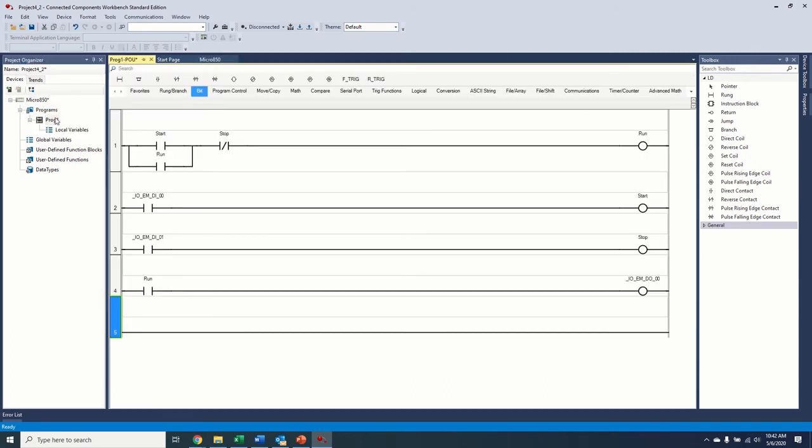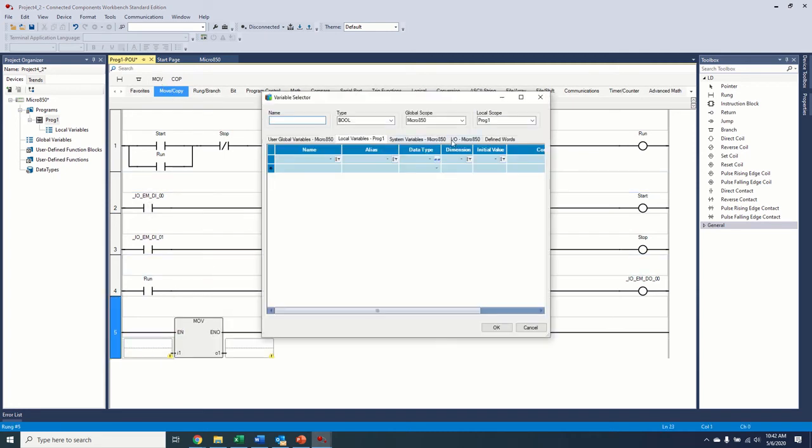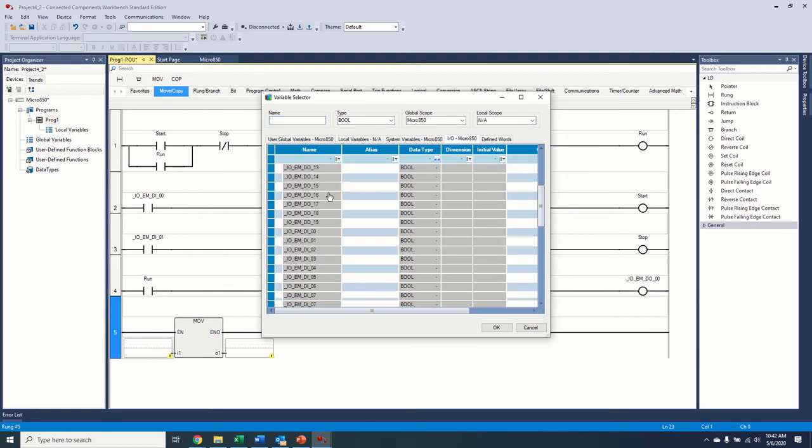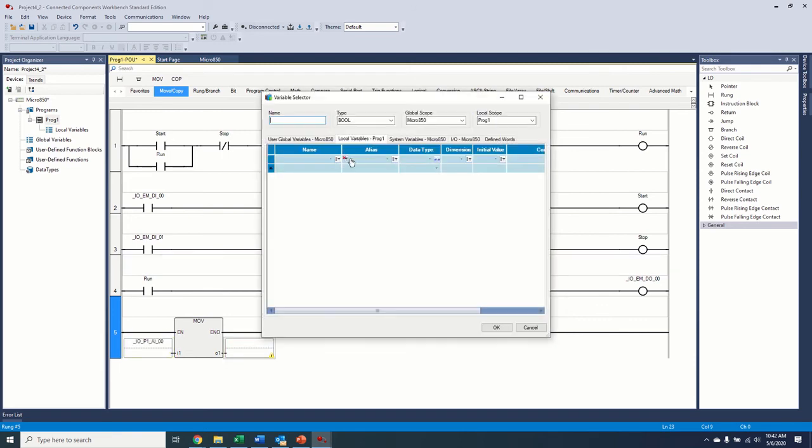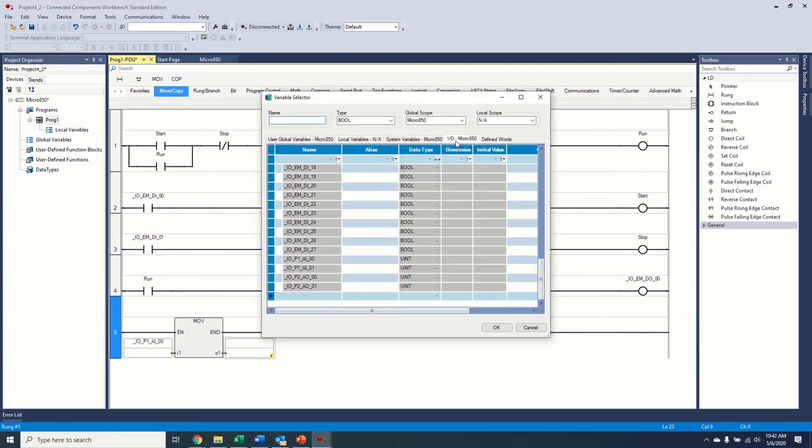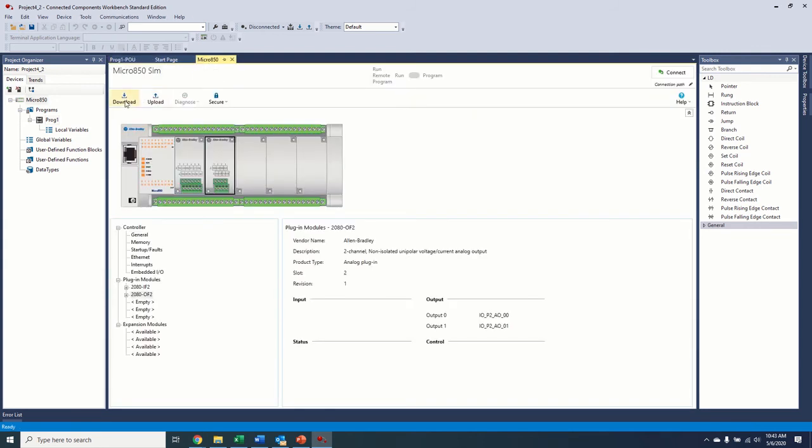So in the micro 850s, their analogs are based on a 0 to 65,535 integer base. So any scaling you want to do with real numbers, you would have to do that. And we will cover that when we get to the drive functionality. But in this case, we're just going to bring our move command in here, brought it in. We're going to move our, you can see our plug-in module, so P1, plug-in module one, analog input one, right into our analog output. There we go, we'll save that, come back to our micro 850 page.